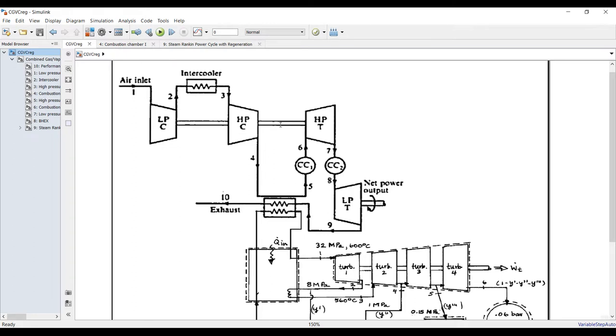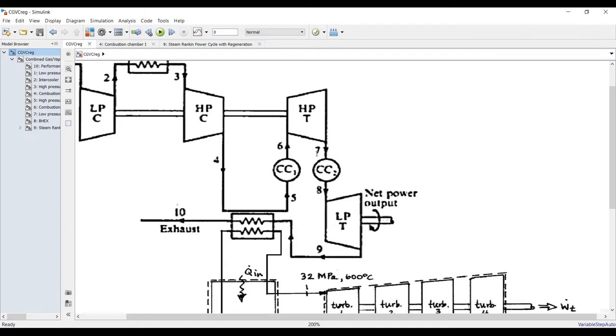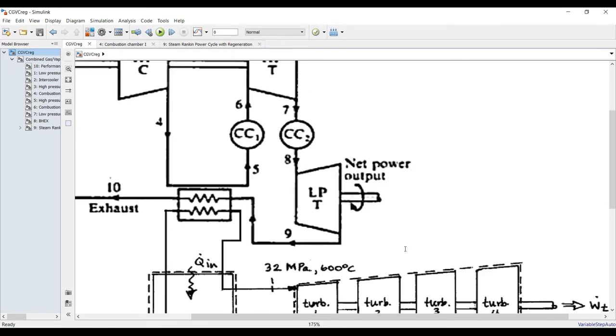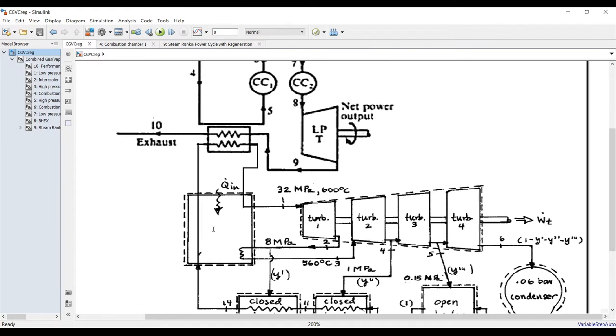The high-pressure compressor is attached to the high-pressure turbine unit. The exit from the high-pressure compressor goes through combustion chamber number one, where enthalpy and pressure are increased by heat addition. Then we go to the high-pressure turbine, which provides mechanical shaft power for the compressors. After that comes combustion chamber number two, adding heat again before the low-pressure turbine, which generates power from the gas cycle.